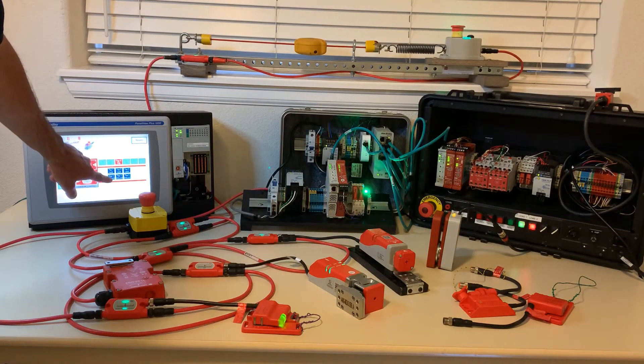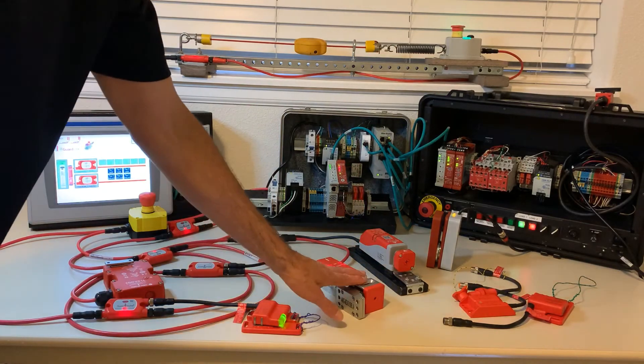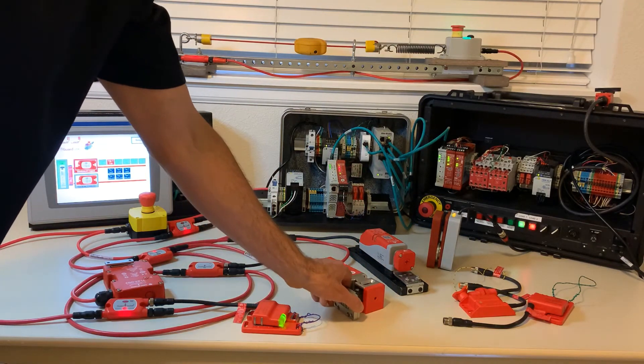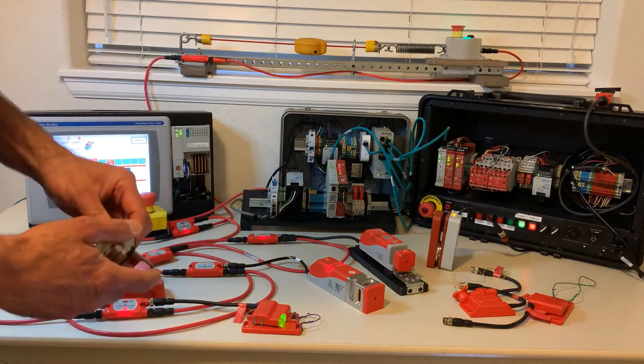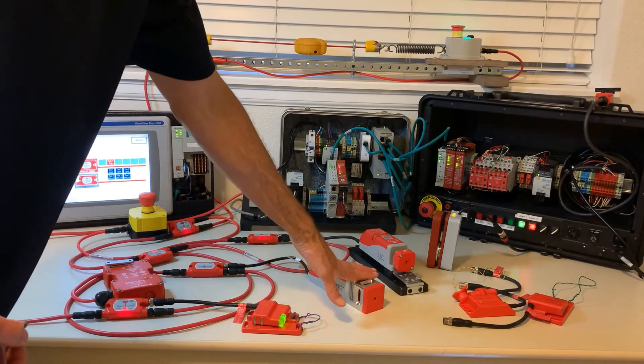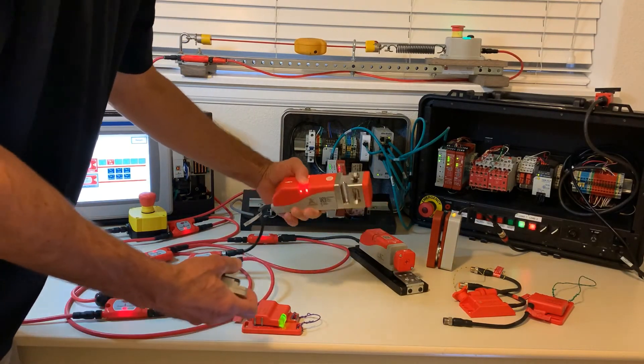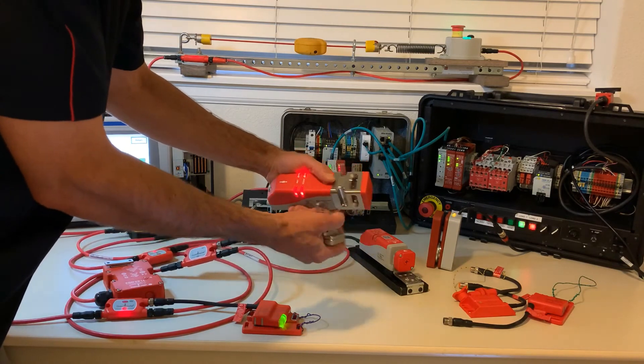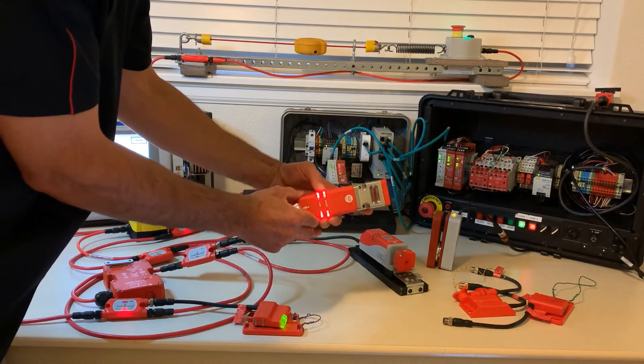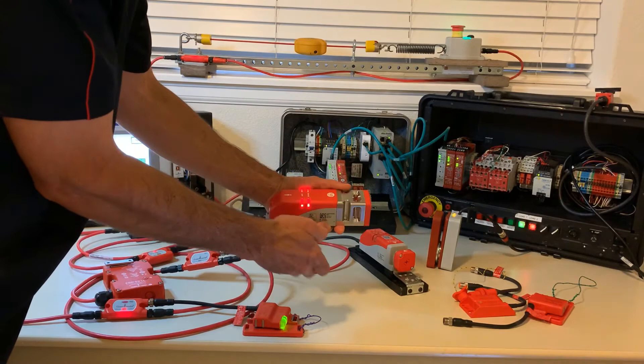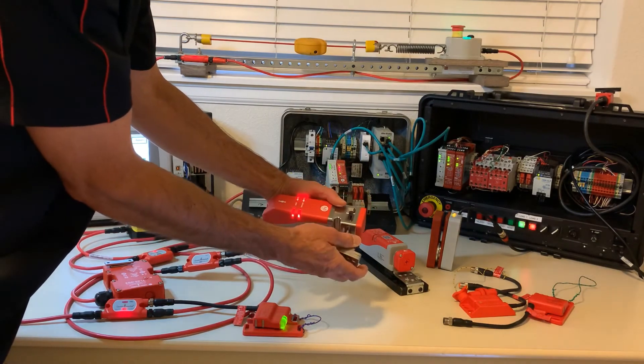On tap 1 we have the 440G MZ with 2500 Newtons of holding force offering the highest level of safety for full body access protection. Category 4, SIL 3, and PLE features highly visible 270 degrees of LEDs for status of the device as well as the link.